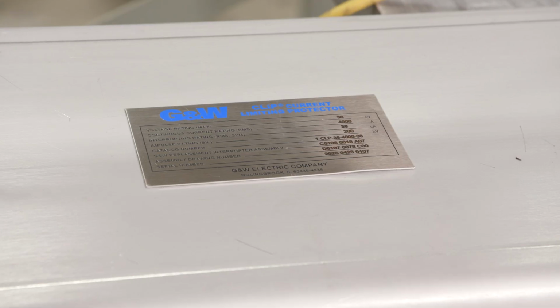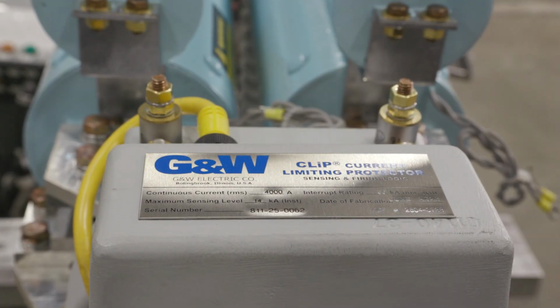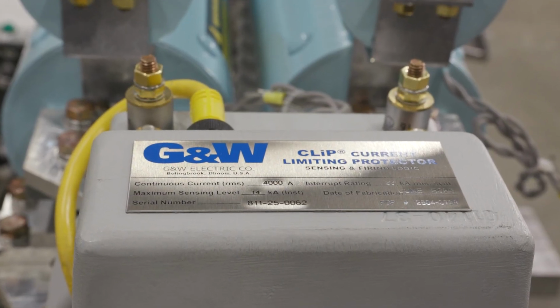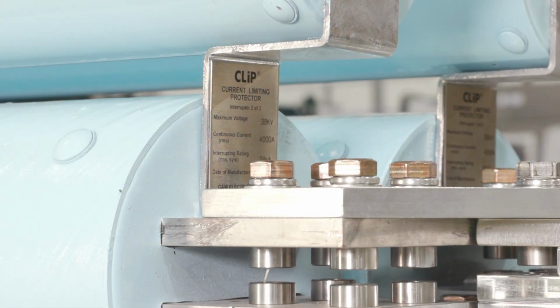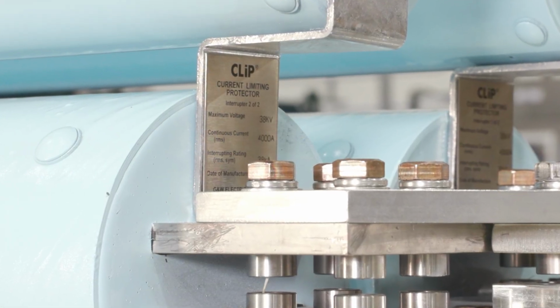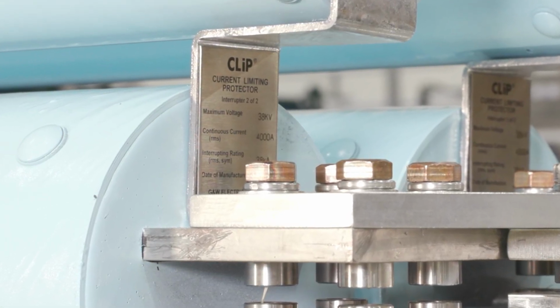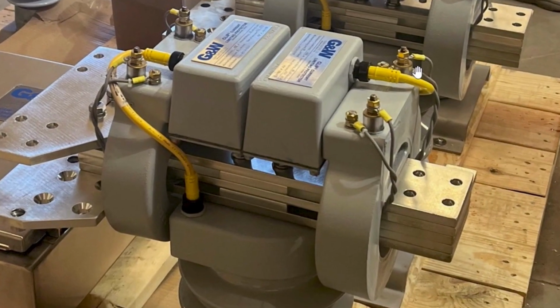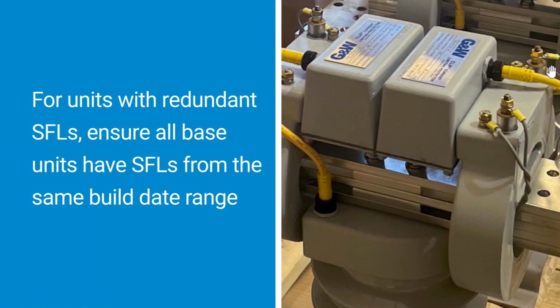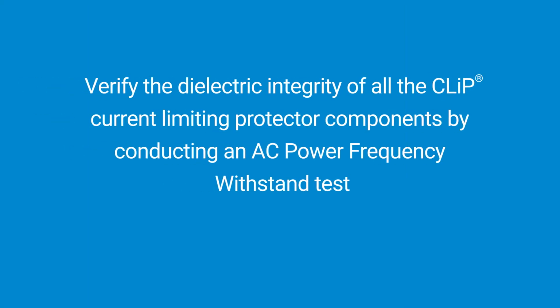Let's begin by inspecting the nameplates on the interrupters, parallel pieces, base plate, and the sensing and firing logic system, or SFL, to confirm that the voltage, continuous current, and fault current ratings match those listed on the purchase order. For units with redundant SFLs, ensure all base units have SFLs from the same build date range. Verify the dielectric integrity of all the CLiP current limiting protector components by conducting an AC power frequency withstand test, also known as a high-pot test.